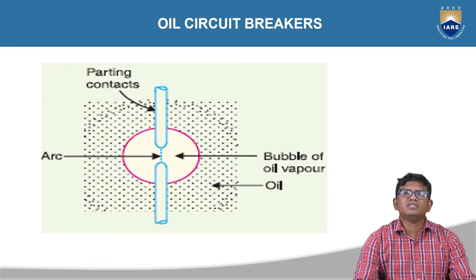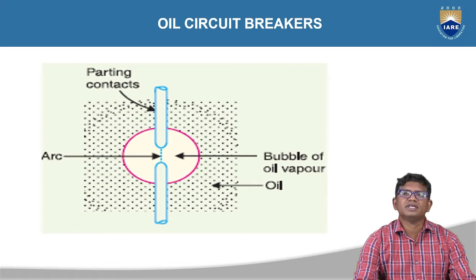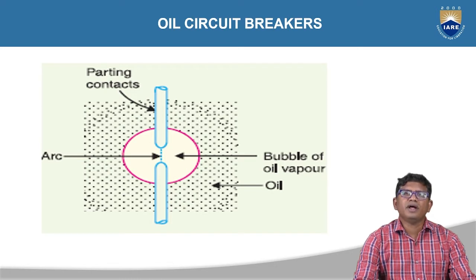The hydrogen gas occupies more space and has high thermal conductivity. It cools the arc. The dots between the two contacts represent the arc. Under abnormal conditions, when the moving contact is withdrawn from the fixed contact, arc is initiated between the contacts of the breaker. The arc is undesirable.